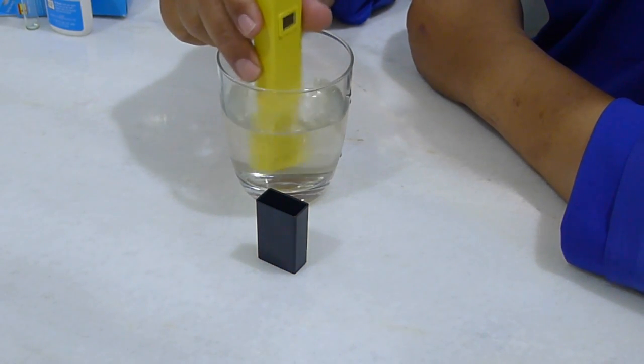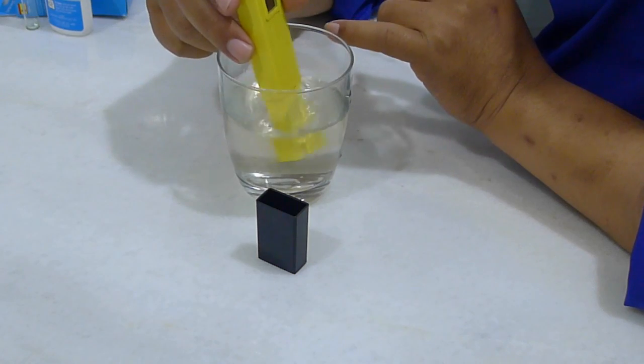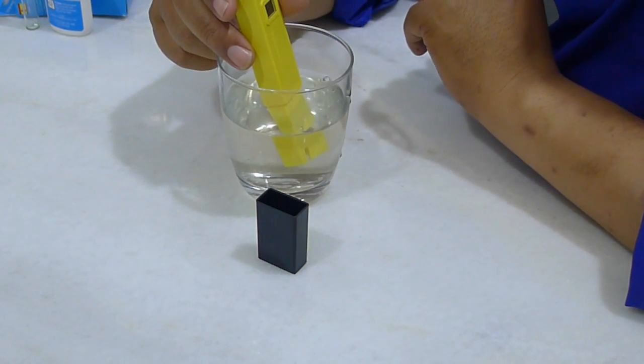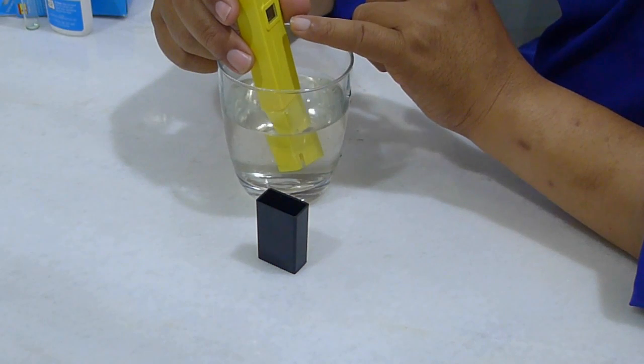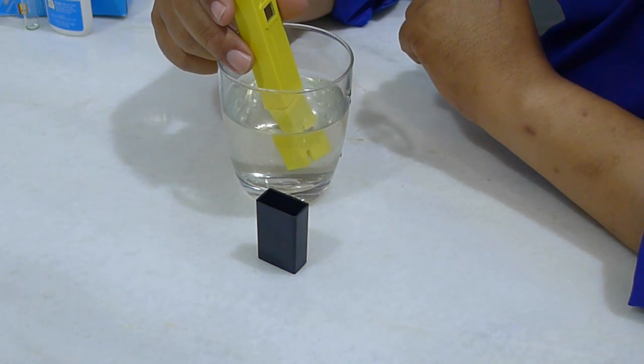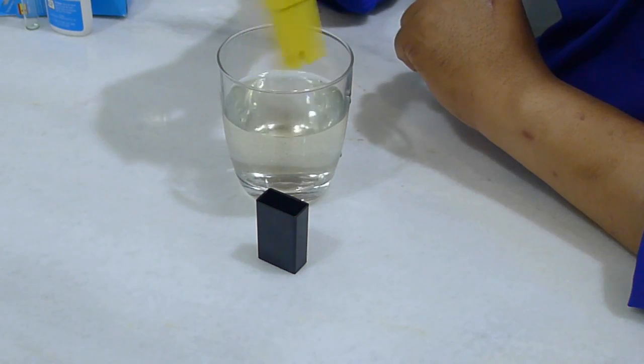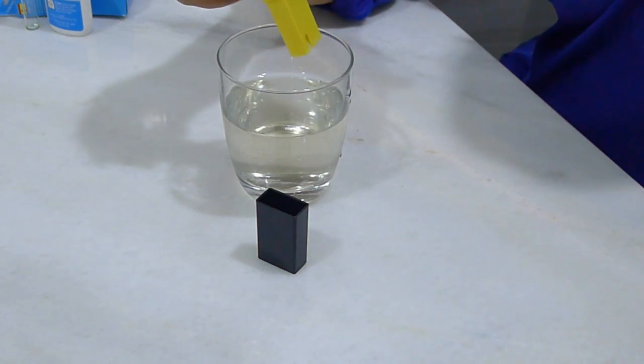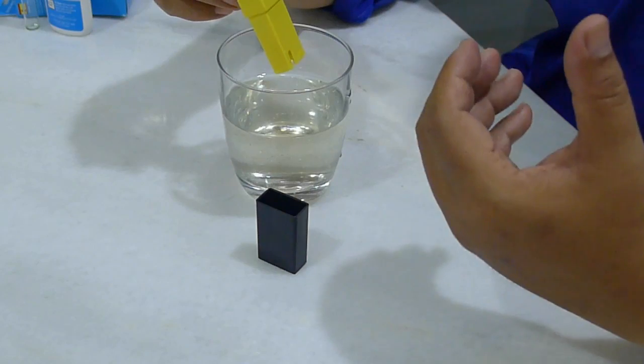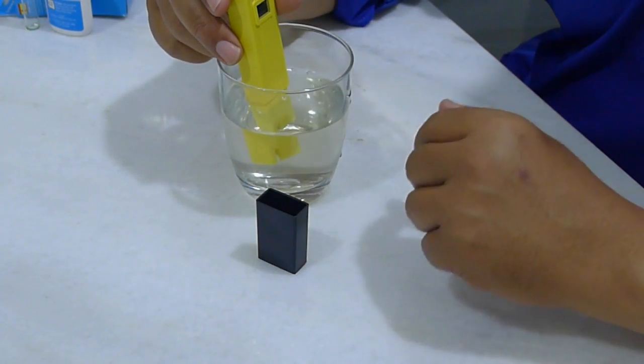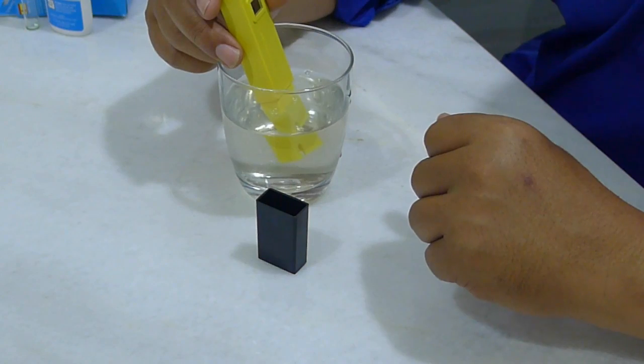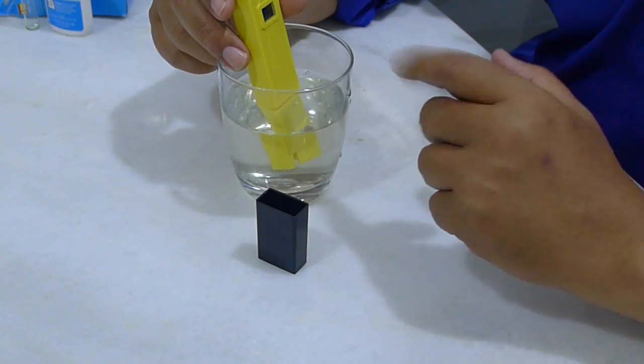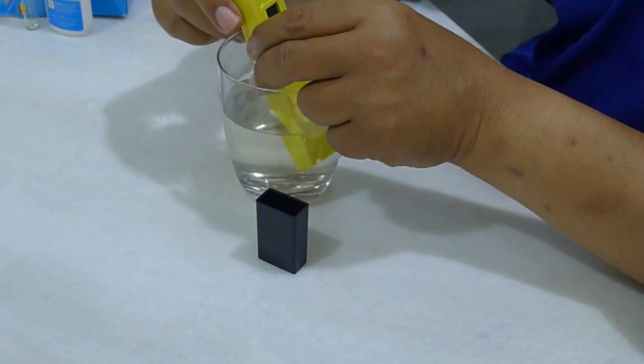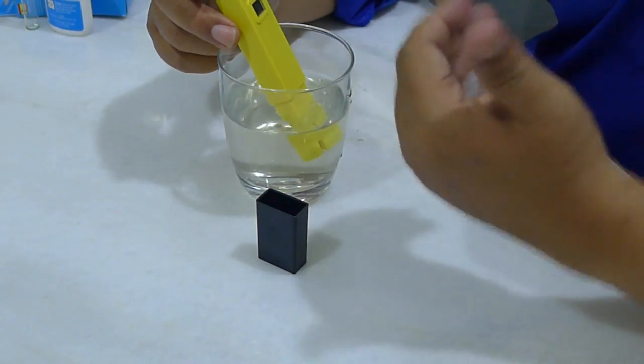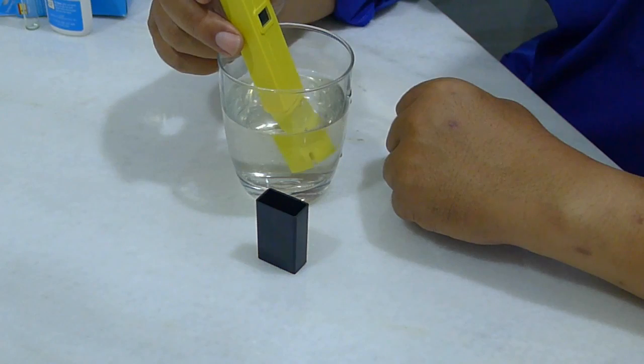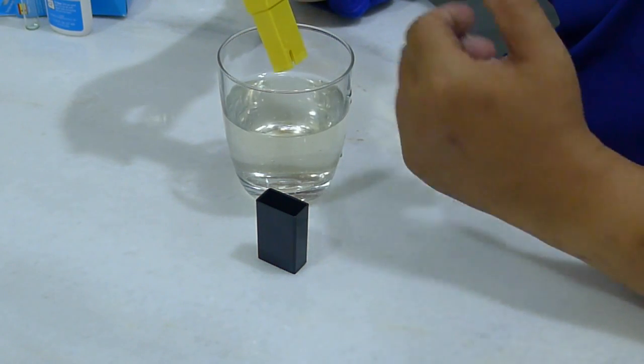Do it again. It's best to read the value while the probe is inside the water. Okay, when it's in, the value is around 6.8. The moment you lift it up, it will sense air and the pH value will start to increase. That's not a good way to indicate pH. So it's best to read it while it's inside the water. So it's around 6.9. There is no hold function that you can hold the value. So the moment you lift it up, it will show some other value.